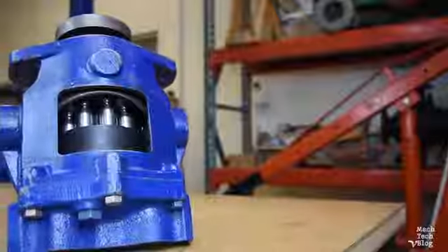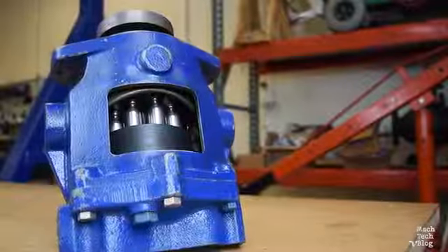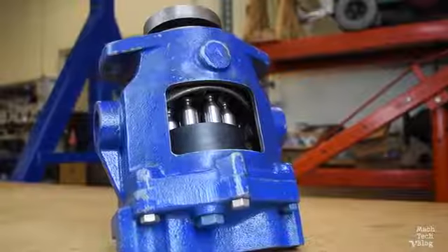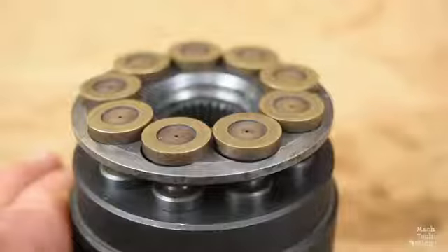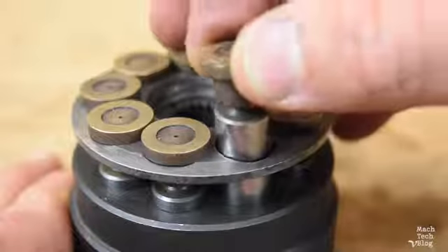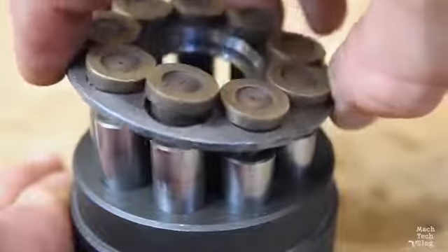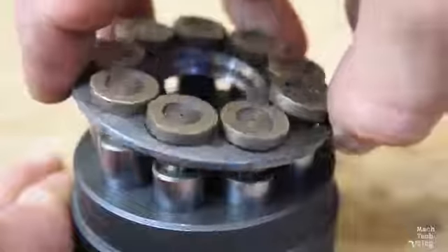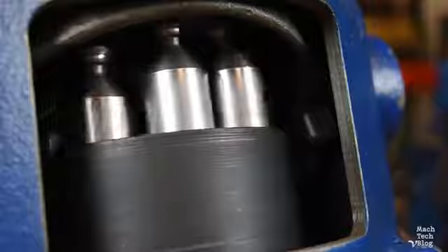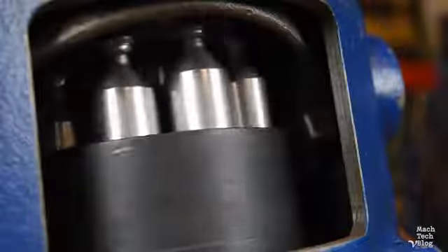Here's an example of a common piston pump called an axial piston pump. This pump is a tad more complex than our little demonstration, but the pumping action is generated in exactly the same way. The axial piston pump has multiple pistons equally spaced on the end of a rotating angled plate. As the plate rotates, the pistons are driven into and out of their respective cylinders. You can clearly see the motion here. Like most reciprocating pumps, piston pumps are relatively efficient and they're capable of generating very high pressures.